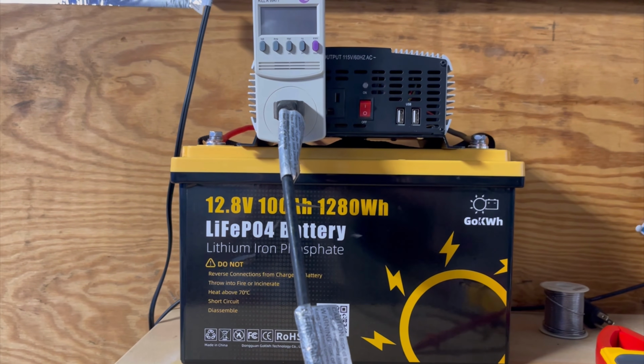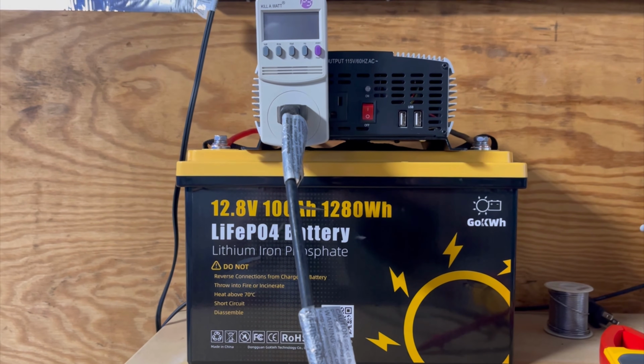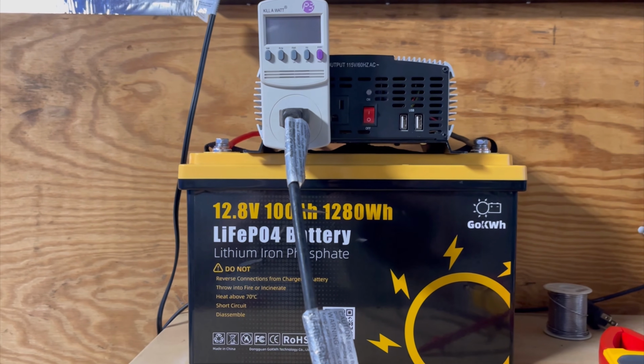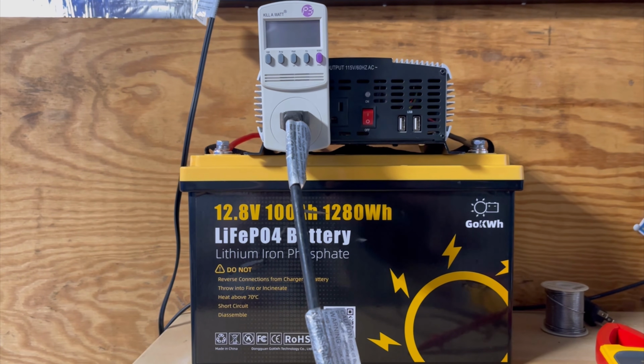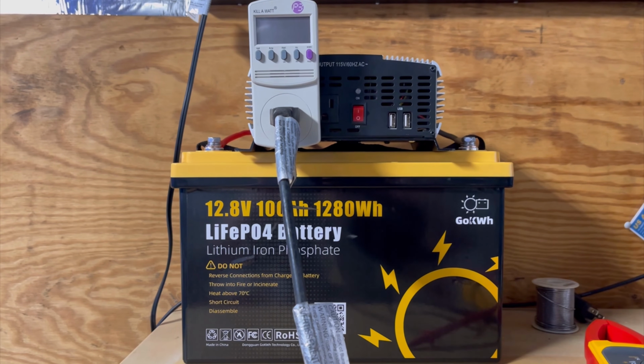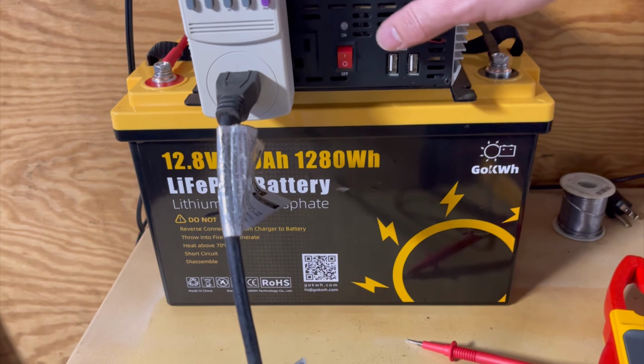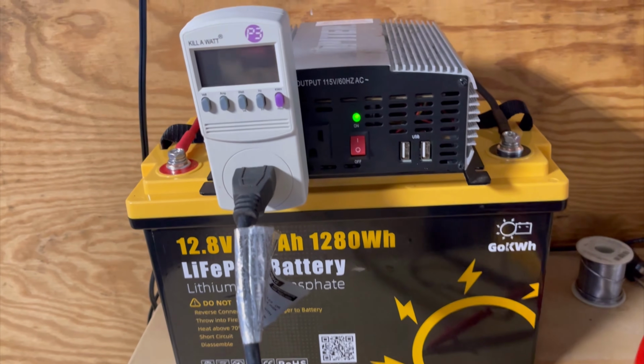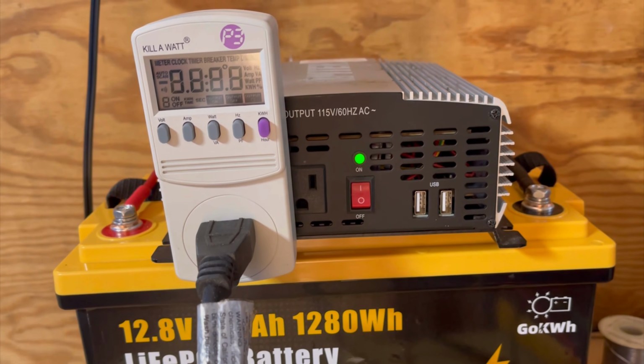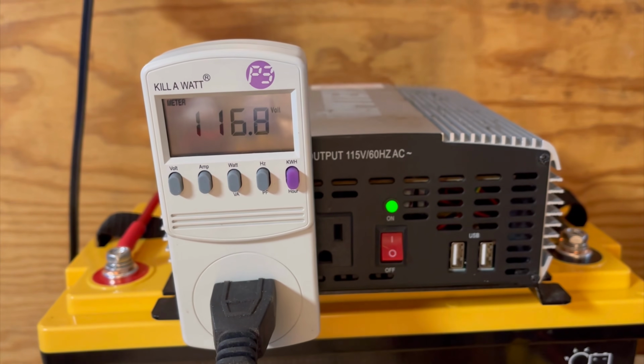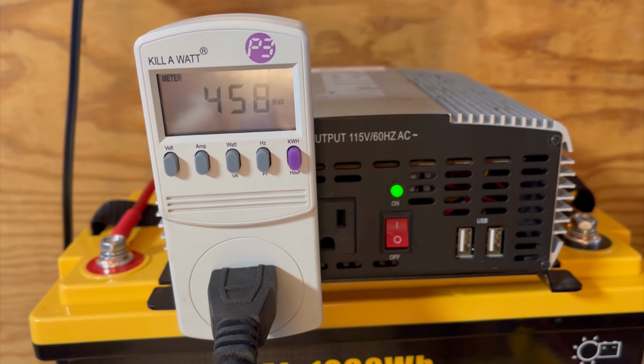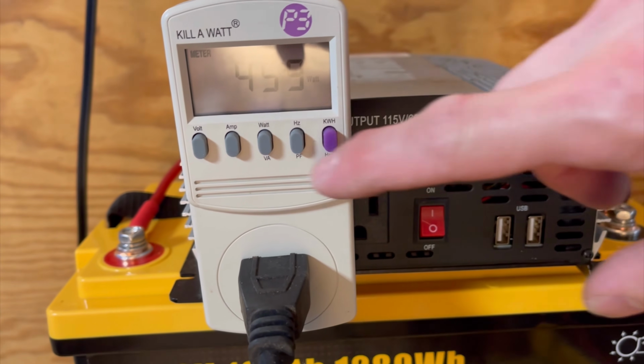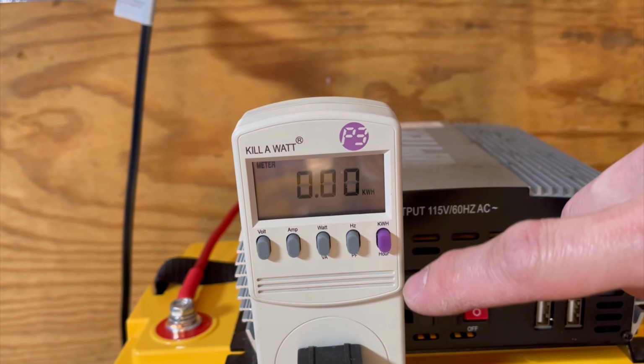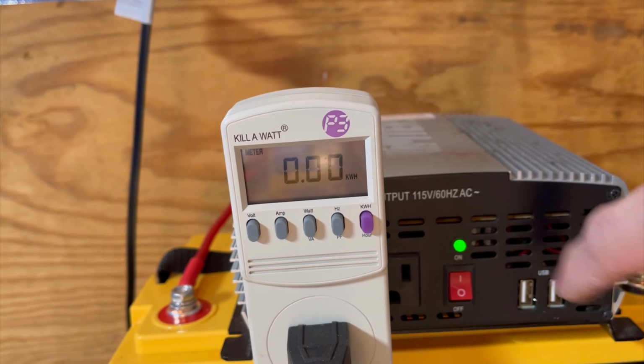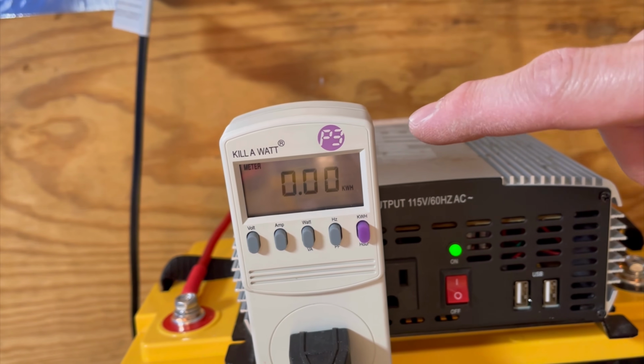We're going to go ahead and flip this inverter on. That's going to power up a 500 watt halogen light, and that's going to be our load to see if we can get this 1,280 watt hours out of this battery. Alright, we're going to flip it on. The light has come on, and we're drawing down 460 watts or so at 3.97 amps. This will give us our reading, and the number we're looking for is 1.28.